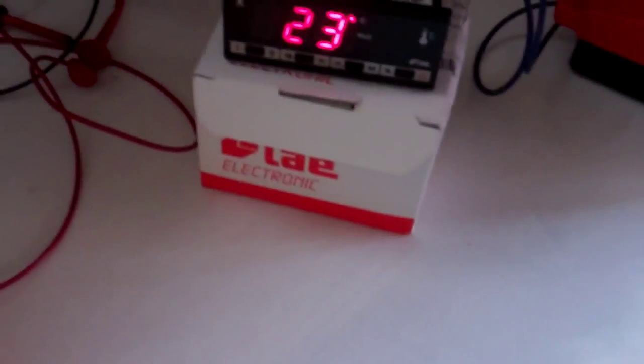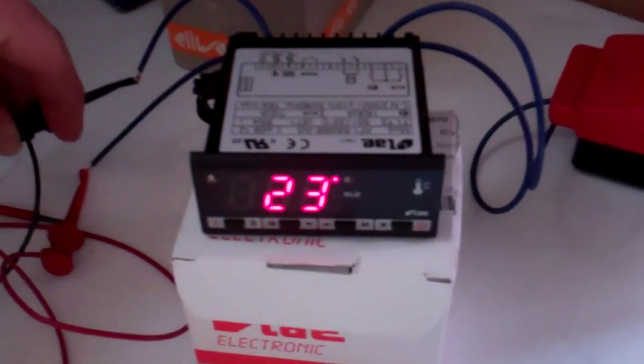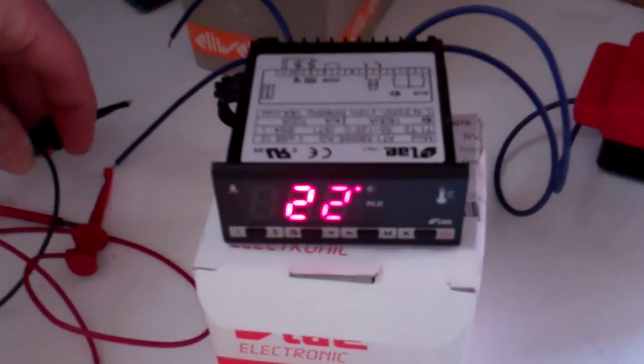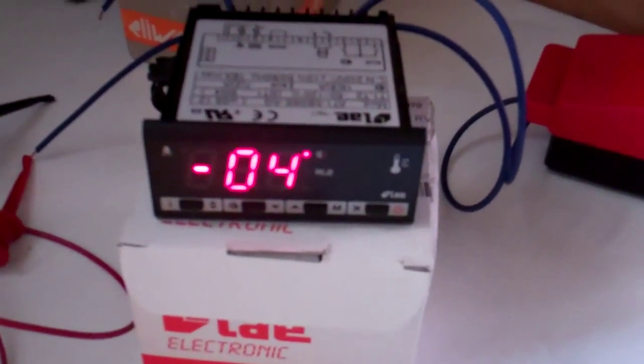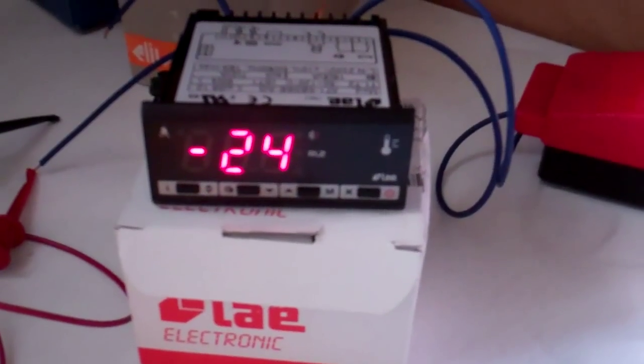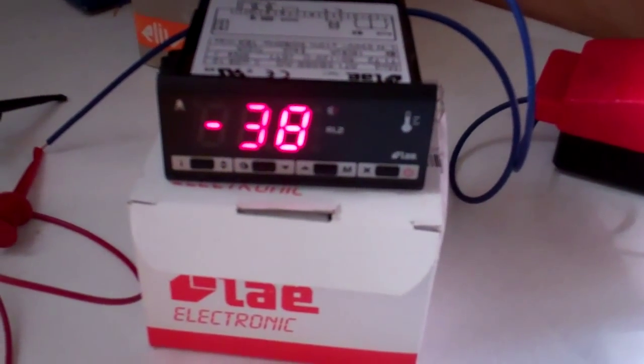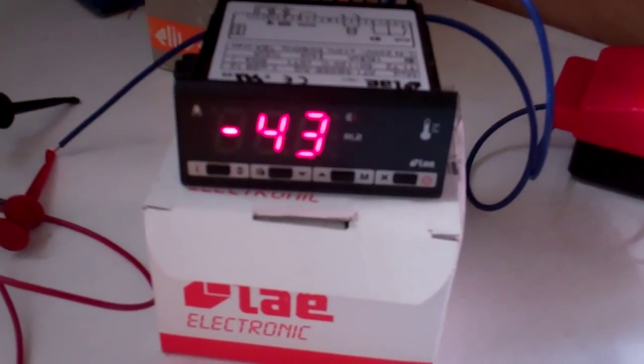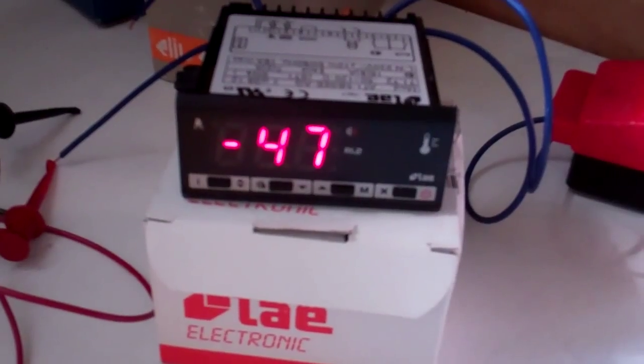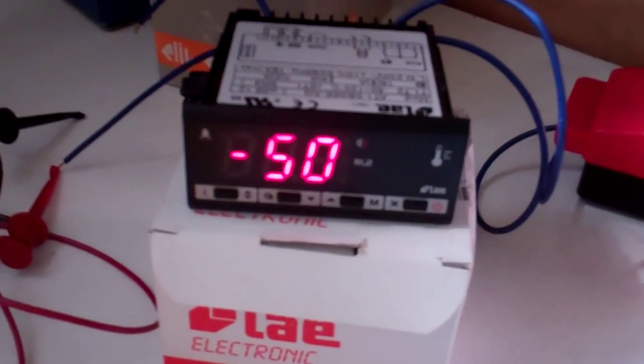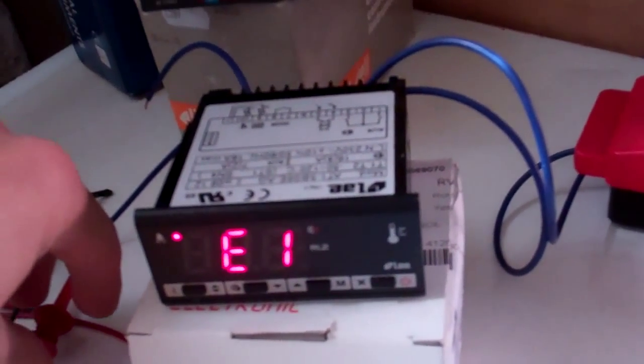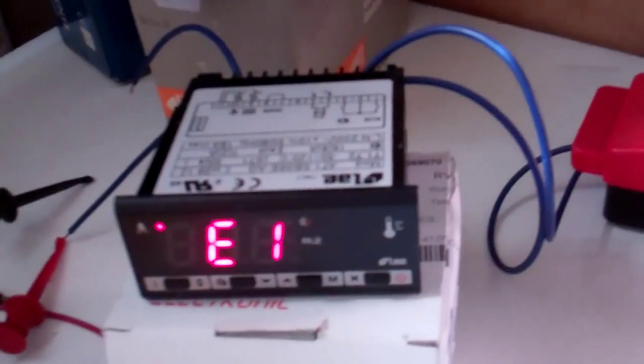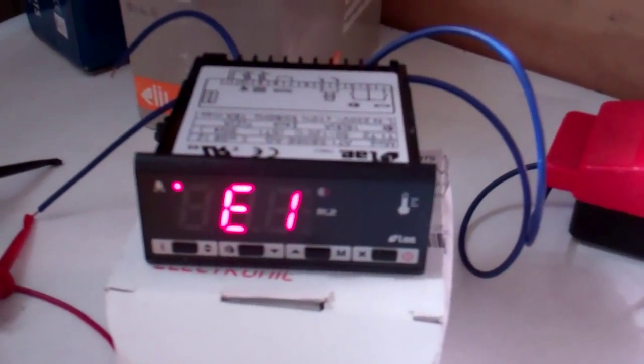I think we'll just show you what happens when the probe went open circuit. There we go. Between minus 50, there we go, E1, probe fault.